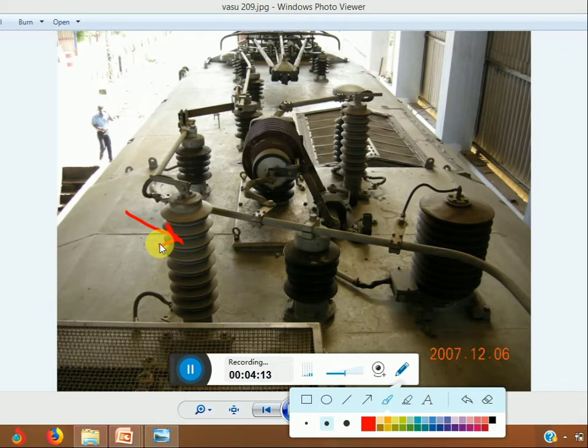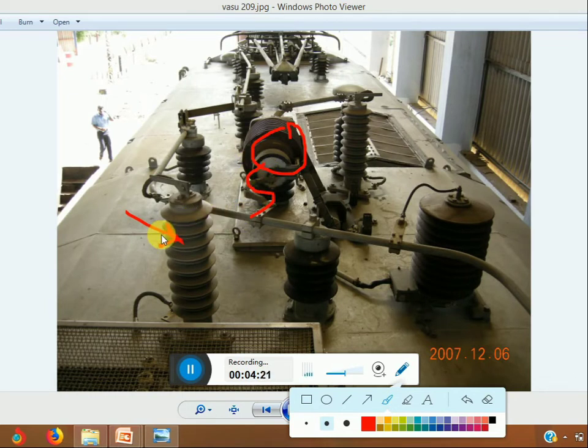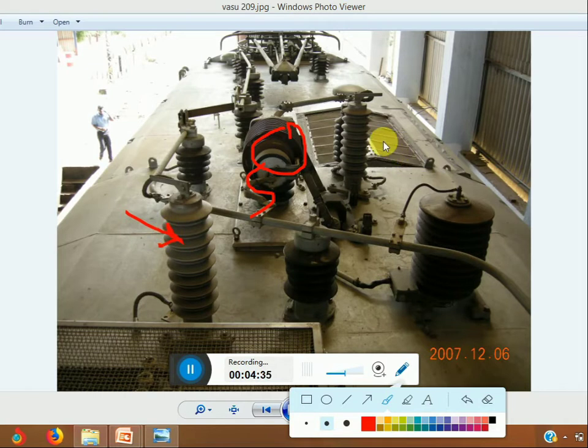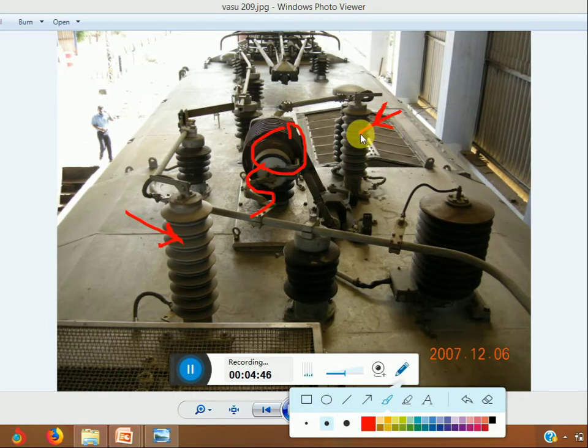ET1 is connected to the center roof bar before the VCB. The supply is going to the VCB; before closing of VCB, ET1 is connected. Any surge voltages before closing of VCB will be grounded through ET1. ET2 is connected after the VCB. If any surge voltages occur after closing of VCB, they will be grounded through ET2. ET1 and ET2 are gapless surge arrestors.